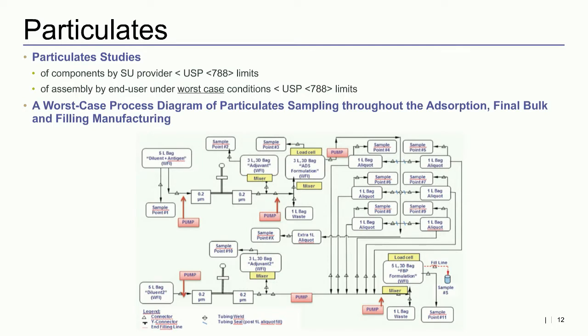The samples at volumes greater than 25 mils were aliquoted into 4 by 5 mil preparations for testing, where the first aliquot was discarded and the last 3 aliquots were measured to obtain a cumulative particle count per milliliter. And the limits for the USP that were used were at particle sizes greater than or equal to 10 microns, there are no more than 25 particles. At particle sizes greater than or equal to 25 microns, there were no more than 3 particles.